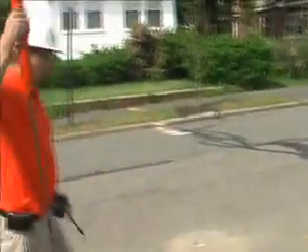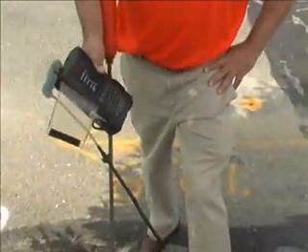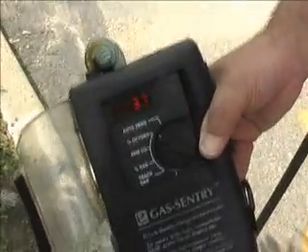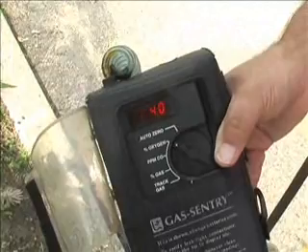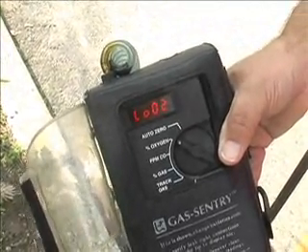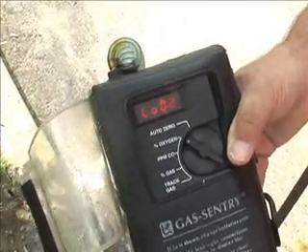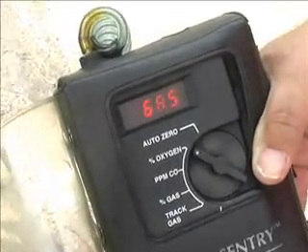And we'll take readings on each side, about 3 feet. 36% gas up this side, but hardly any on the other side. Right, because the service line's right here, going this way, and the leak, I think, was up this way. So now we have a very low oxygen reading over here, 3.6. But right at the tree, there wasn't gas. So as this tree grows and gets bigger, it's going to be getting into this unhealthy area in a short period of time.